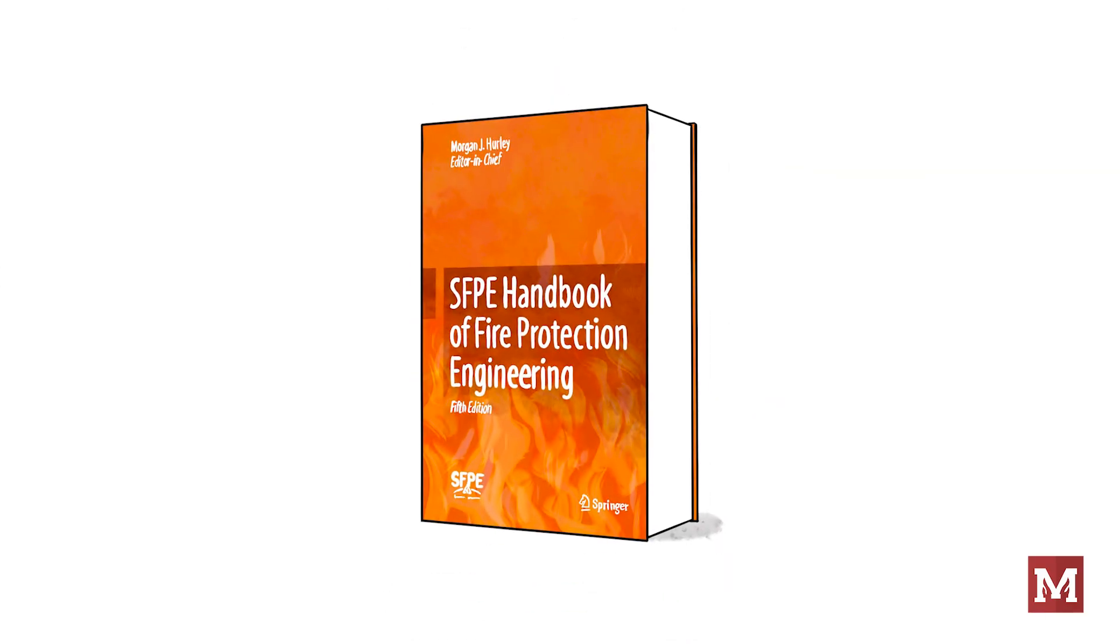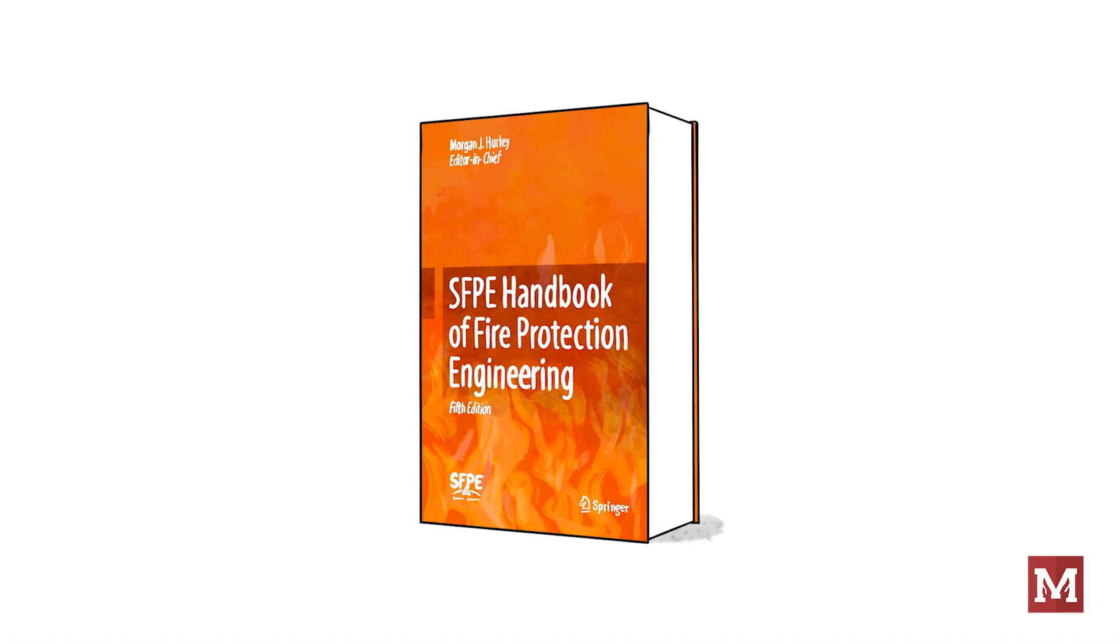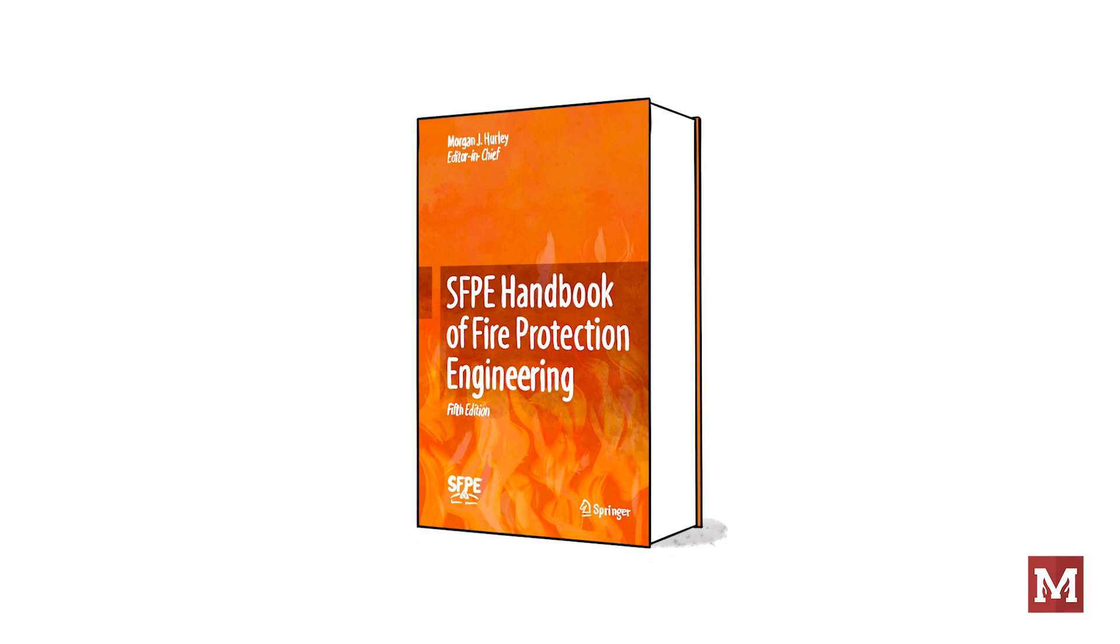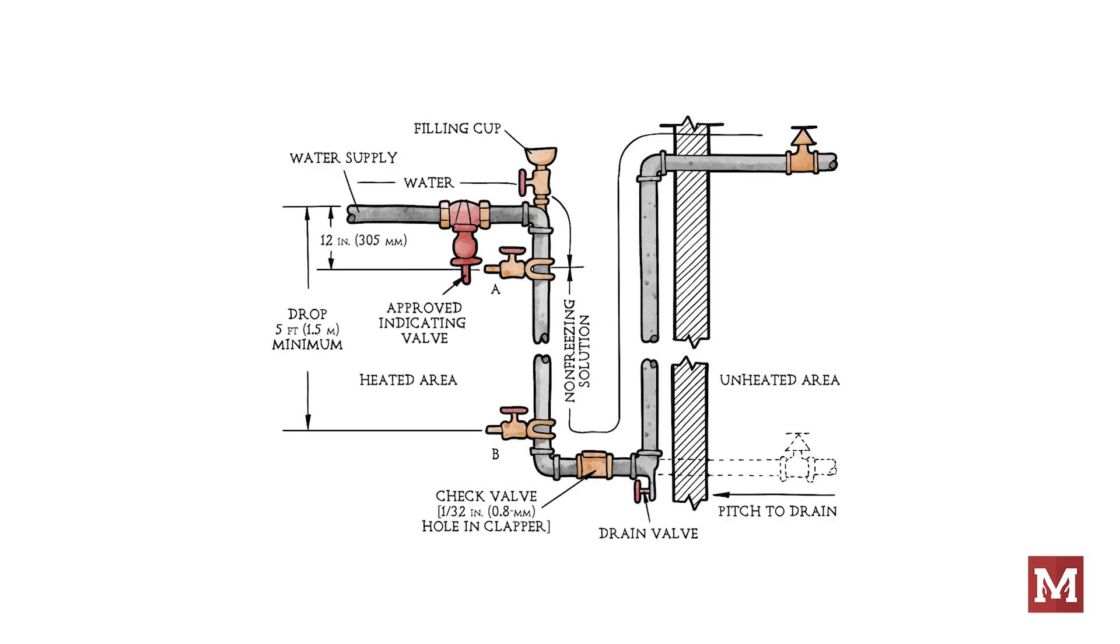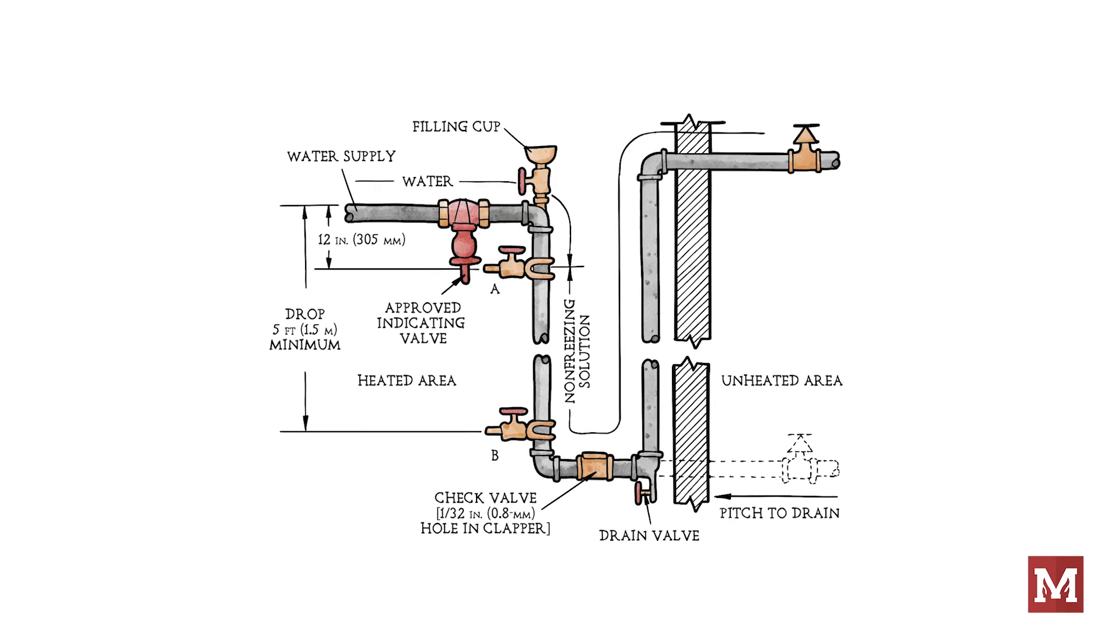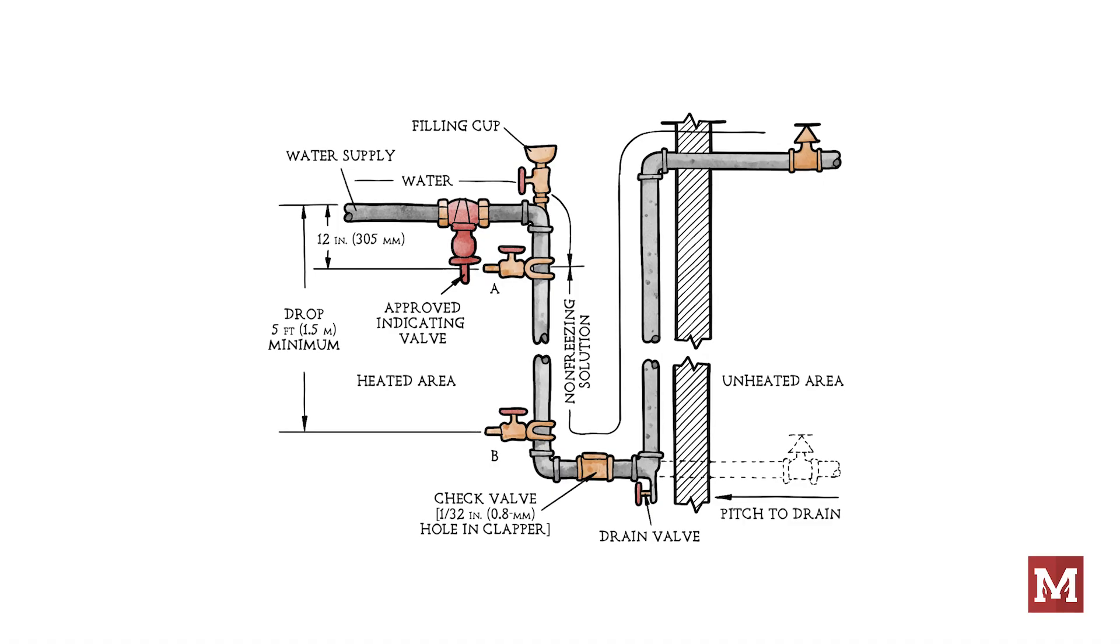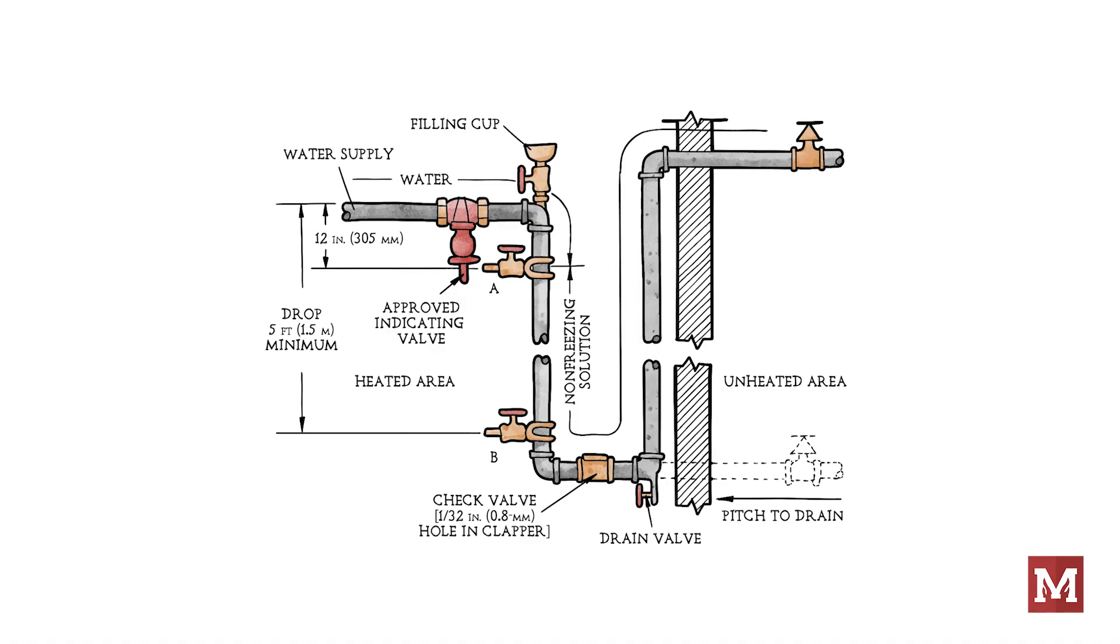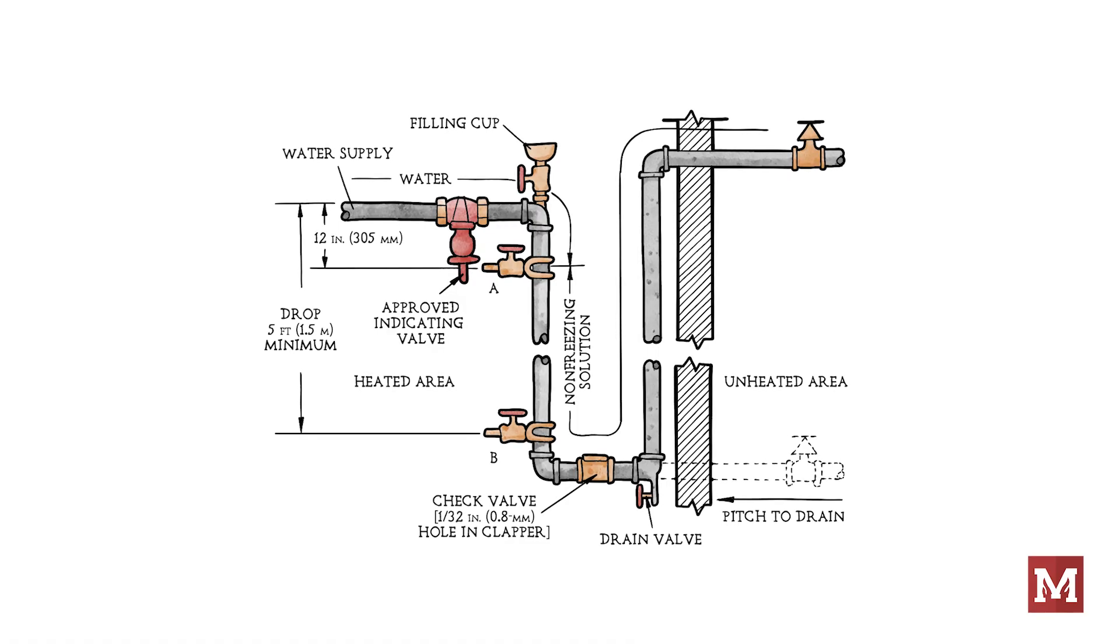So first let's get some background. Ken Isman is with the University of Maryland Fire Protection Group and he wrote in the fifth edition of the SFPE Handbook. The Darcy-Weisbach method is specifically required when designing large antifreeze systems. The reason for this is that antifreeze solutions can have significant changes in viscosity and density, especially in colder environments.